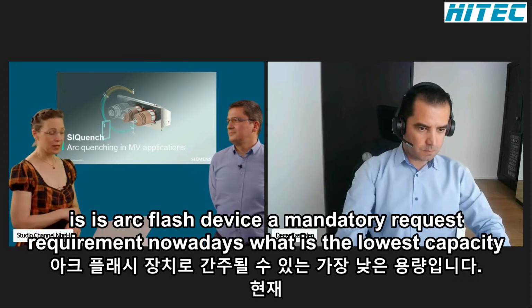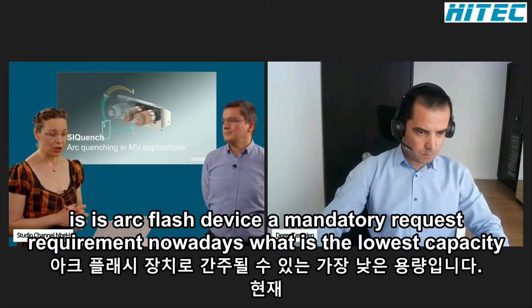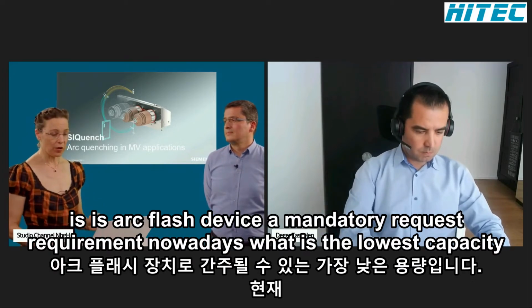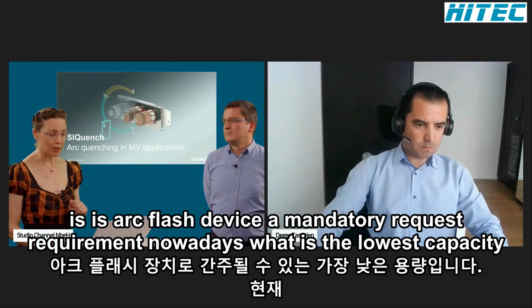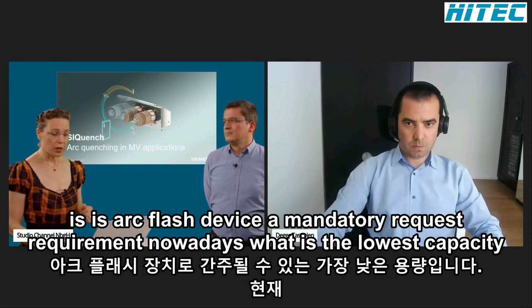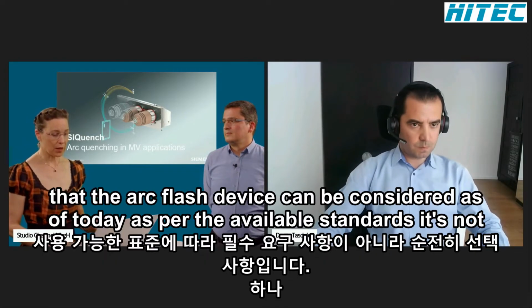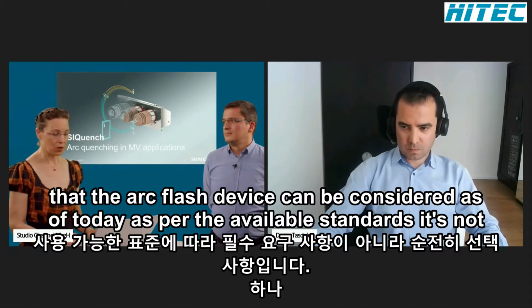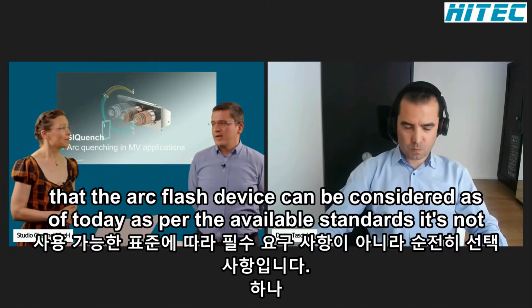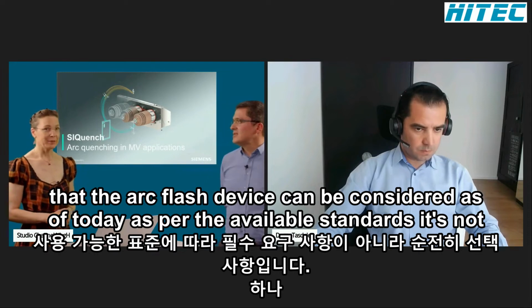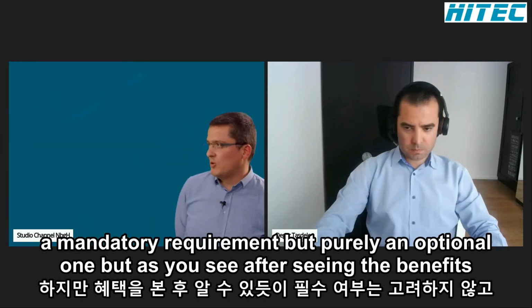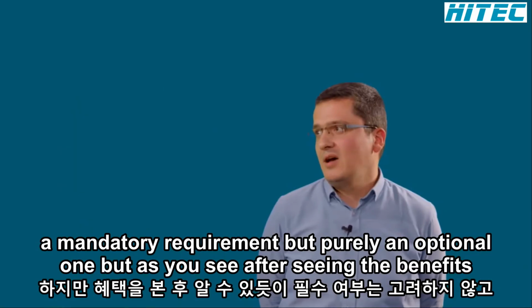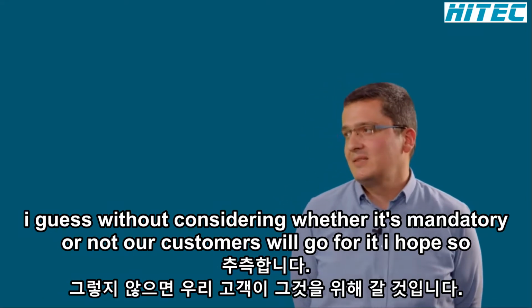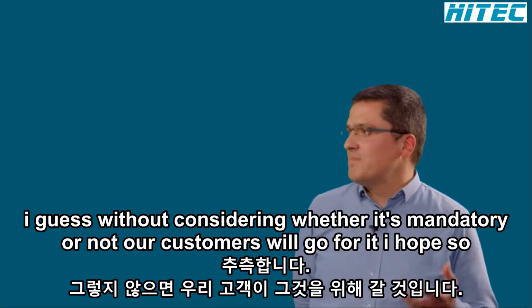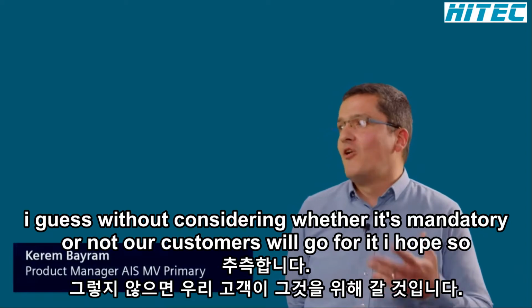So the first question is: is an arc flash device a mandatory requirement nowadays? What is the lowest capacity at which the arc flash device can be considered? As of today, as per the available standards, it's not a mandatory requirement, but purely an optional one. But as you see, after seeing the benefits, I guess without considering whether it's mandatory or not, our customers will go for it.